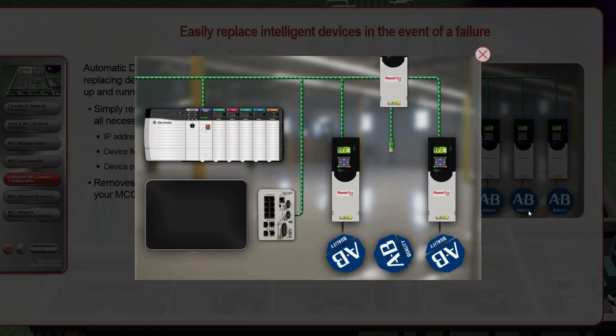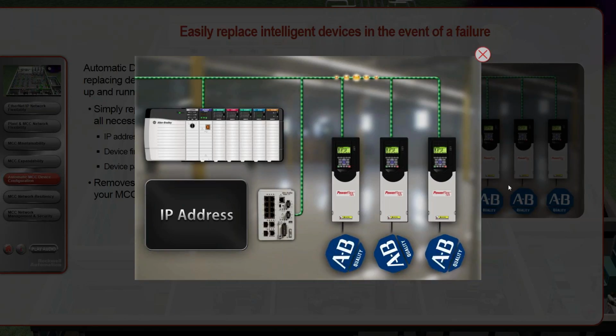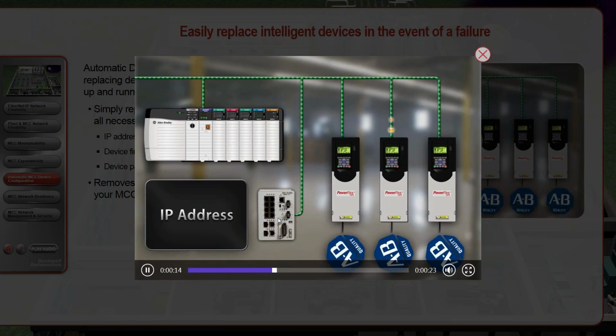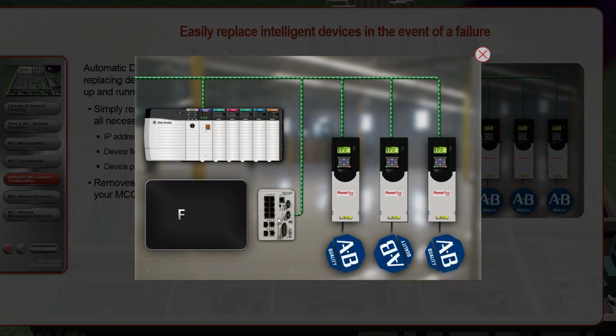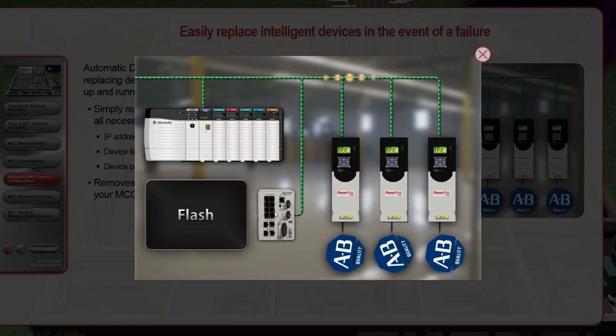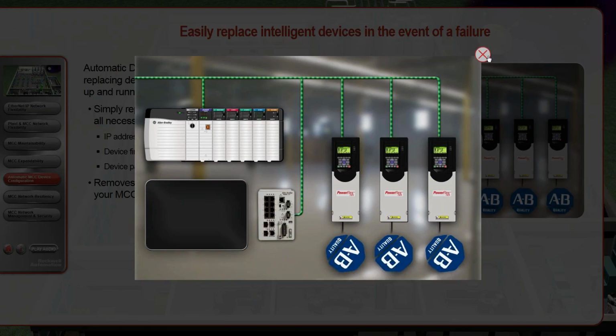The E300 overload relay is also one of those. If there's a failure, the switch can bring port persistence, assigning the right IP address to the device plugged into that port, flashing it the right firmware, and configuring it appropriately so your application gets back up and running. This is supported by a variety of our intelligent motor control devices, though not all, and we find this to be a strong suit in terms of expandability and maintainability of our MCCs, especially when operating within the Studio 5000 Logix Designer environment.